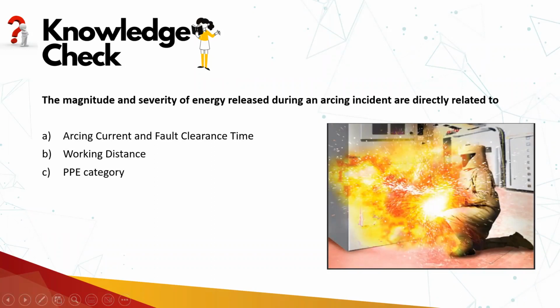Sir, in case it was incident energy, it is still about the source, right? Incident energy is something like the impact on us from the source, so it will cover both. It will be dependent on the arcing current, fault clearance time, and the working distance. So just remember the PPE category table, which talks about the fault current, the device clearance time, and the working distance. That's how we are calculating the incident energy.